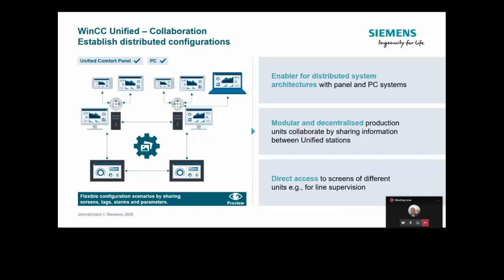In the scenario where an end user has multiple OEM-provided machines on a line, maybe they don't need to be engineered as a single solution. We can use the collaboration option for WinCC Unified to bring these together at runtime. This allows, for instance, a PC-based system to view screens that are actually only defined on a panel. In the first step, we support sharing screens. With future versions, we'll also be supporting tags, alarms, and recipe parameters — the ability to share data seamlessly without having to explicitly engineer it beforehand.